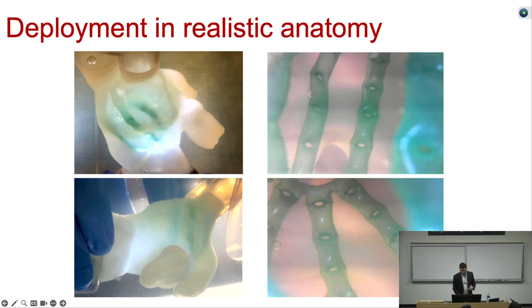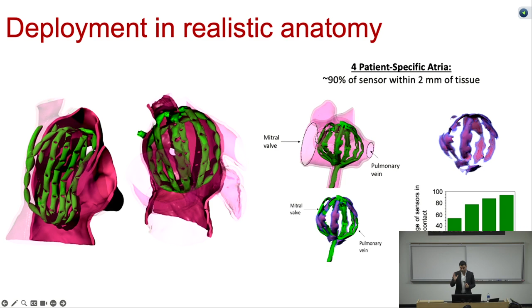And then we characterized how much these electrodes actually come into contact with the tissue. Within these 3D printed heart phantoms, we did a micro CT, and then we showed how many of the electrodes are within a couple millimeters, which is enough to get an electrogram. We saw that we can get at least 80 to 90% of the electrodes in contact, whereas the traditional basket catheters were getting 40 to 50%.